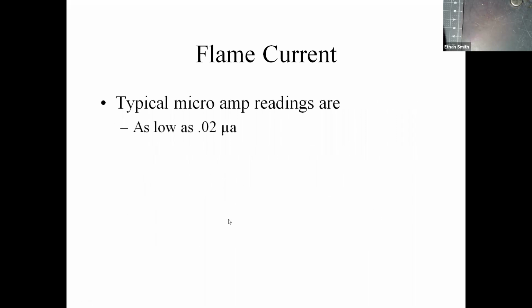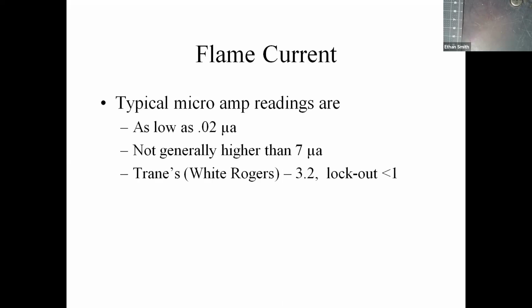Okay, so a typical microamp may be as low as 0.02. This is generally not very good. And generally, we're not going to see higher than 7 microamps. So you'll see this on some commercial equipment. Radiant burners tend to get a little higher microamp reading. Typical furnace is going to be around 3 to 3.5, and most of them lock out below 1 microamp. Okay, we measure that with a microamp meter, which again, on your meter is that little U shape with an A, okay, on your meter.